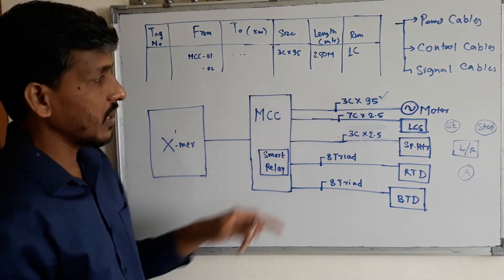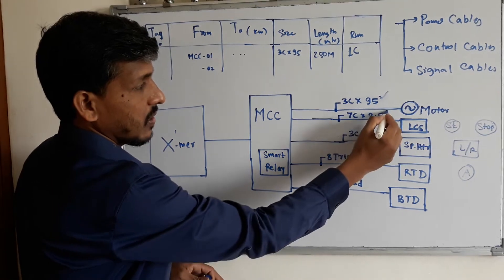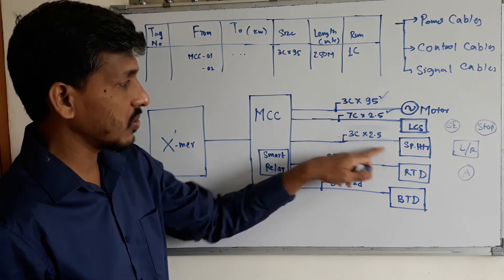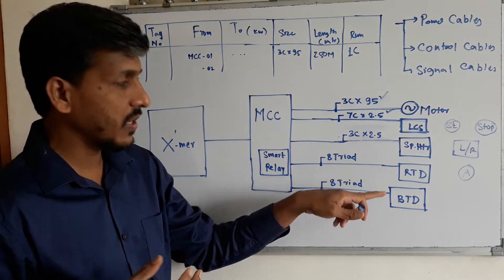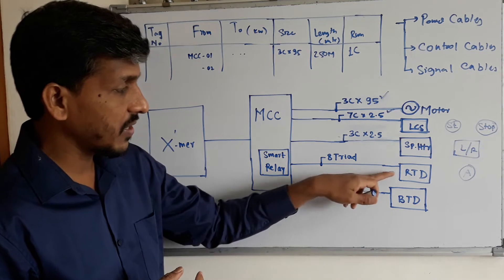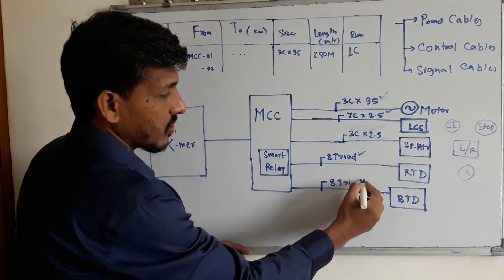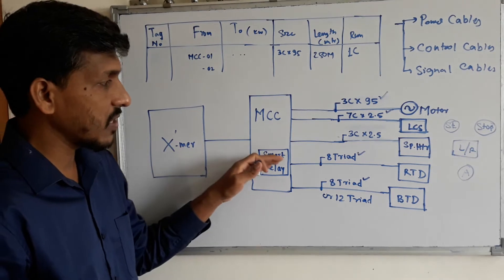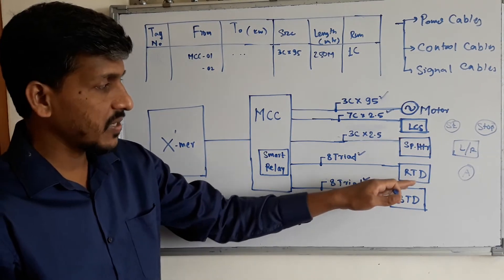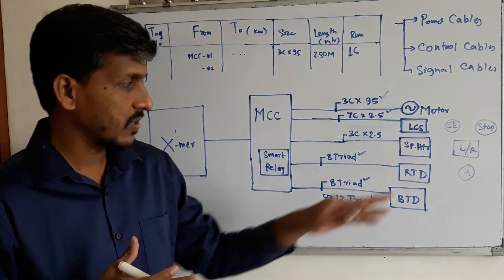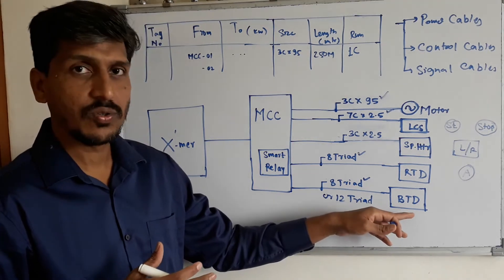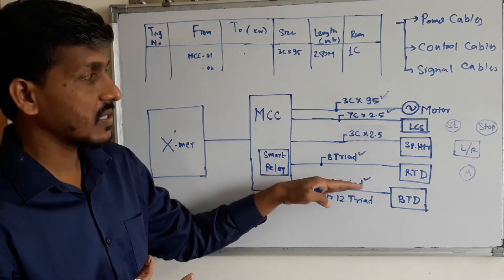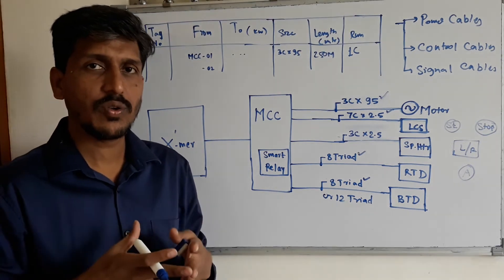For a motor, the power cable could be a 3-core 95mm² cable. Then there is the LCS control cable, which is a 7-core 2.5mm² cable. Third is the space heater cable, which is a 3-core 2.5mm². Depending on the motor rating, there are also RTDs and BTDs in the motors, requiring signal cables such as 8-triad or 12-triad cables. These connect from your marshalling rails to the RTDs and BTDs. RTDs measure the temperature of the windings, while BTDs measure the bearing temperatures of the motors.